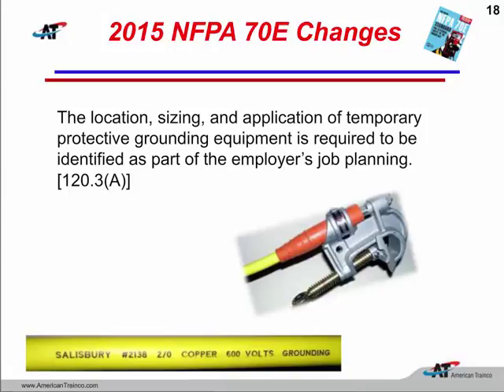Another change that was in Article 120, and Article 120 is establishing that electrical safe work condition. This is step number 6, when we have to install ground straps in the event that there might be any type of chance that the equipment can become re-energized, either with induction or with capacitance. Then we're going to have to install these ground straps.